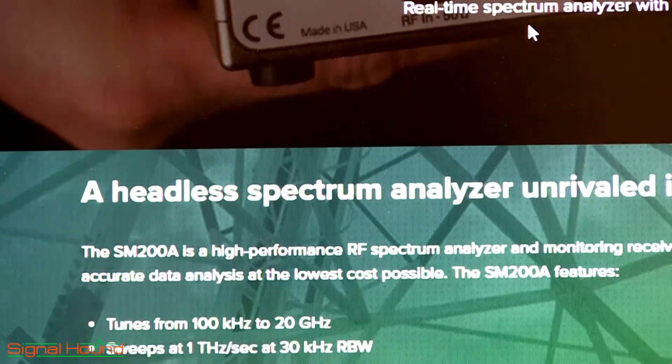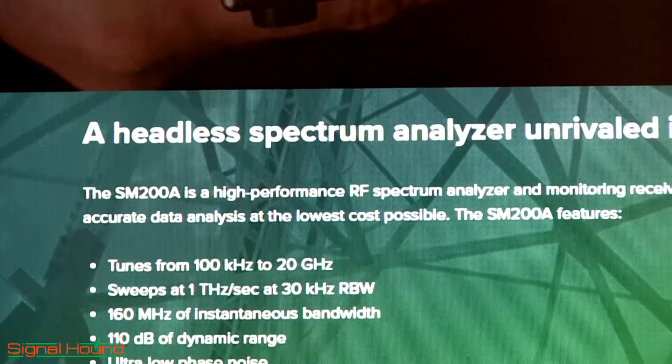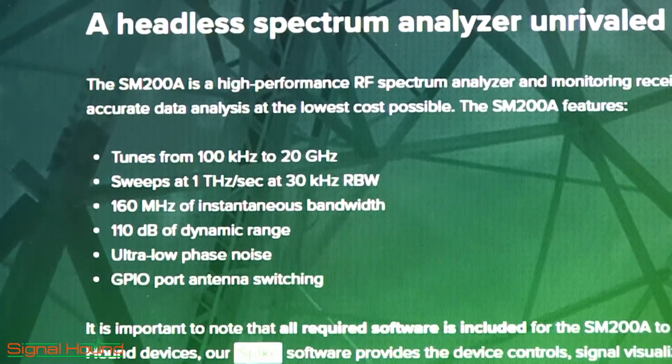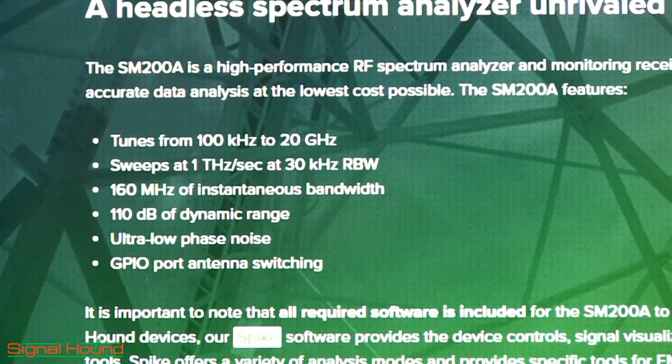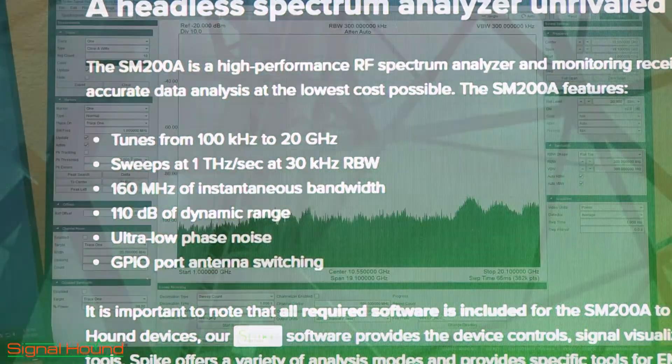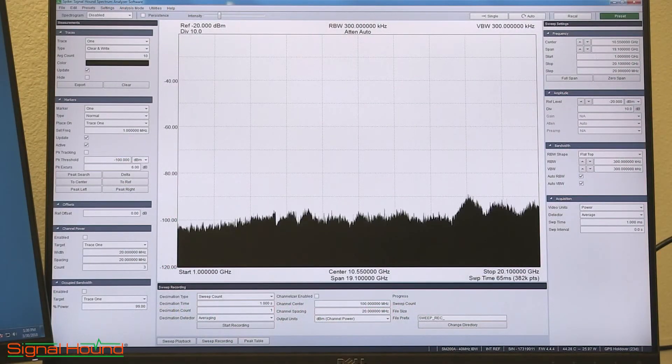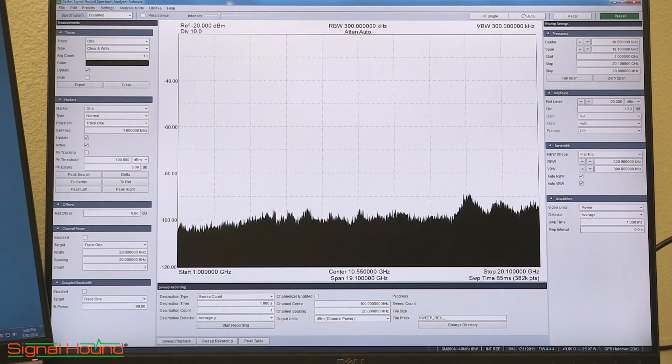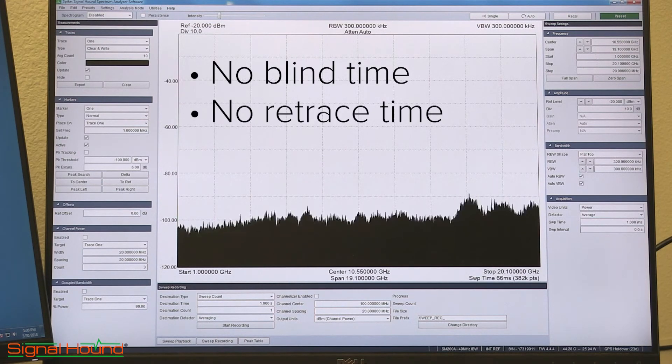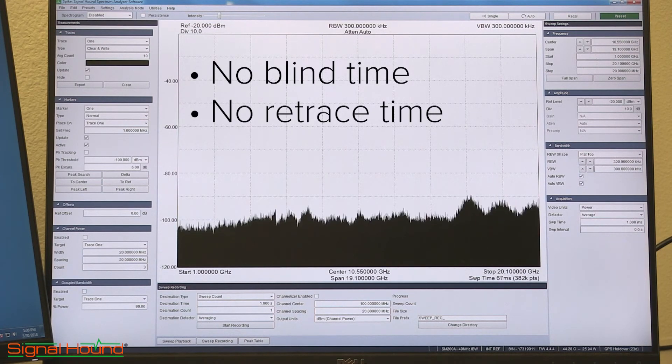One of the most compelling features of the new SM200A spectrum analyzer is the 1 Terahertz per second sustained sweep speed. This is different from other fast spectrum analyzers in that the SM200A suffers from no blind time or retrace time between sweeps. This is due to a very agile local oscillator in the SM200A.